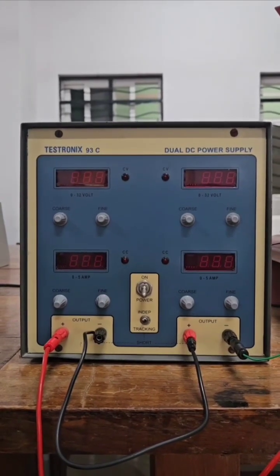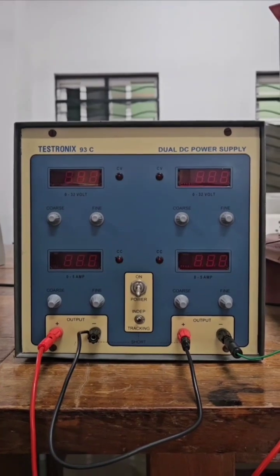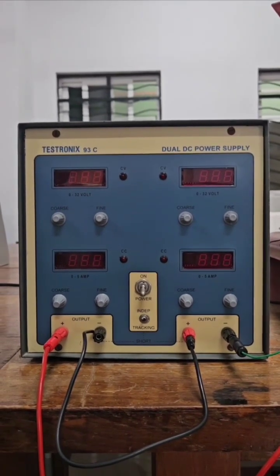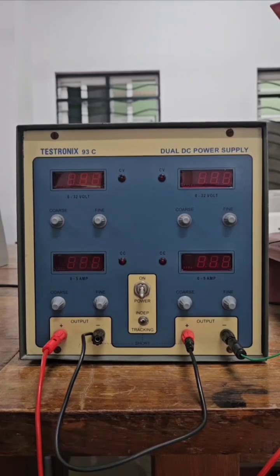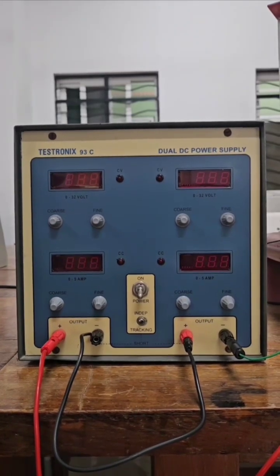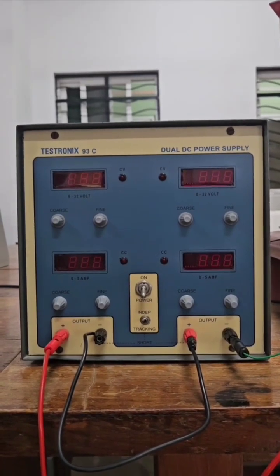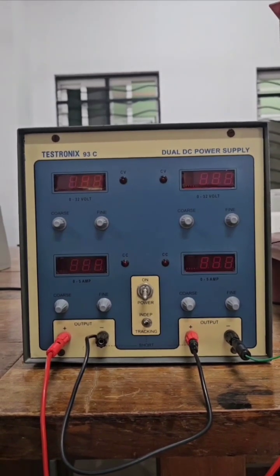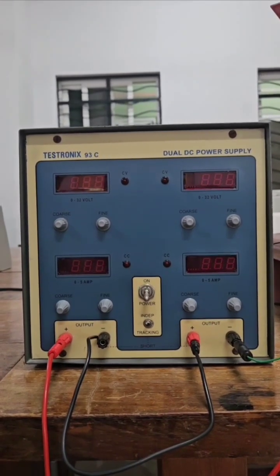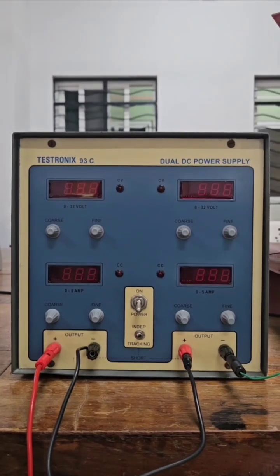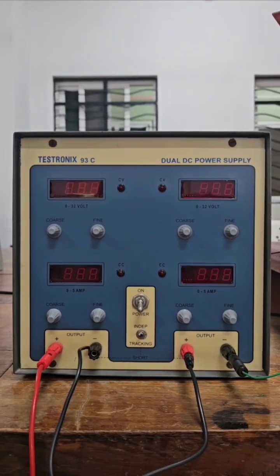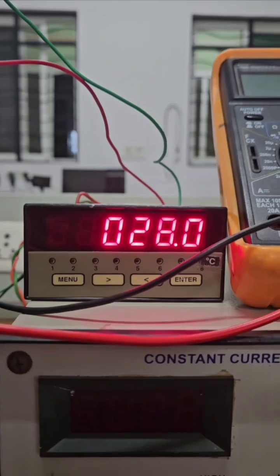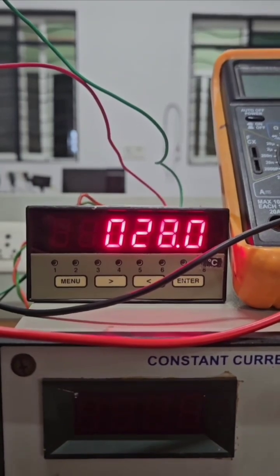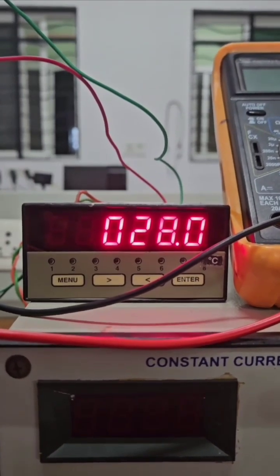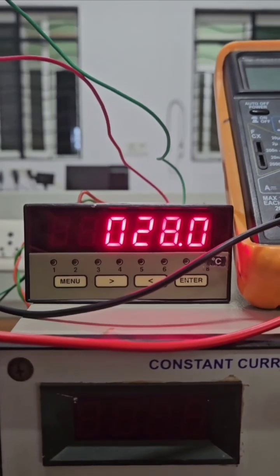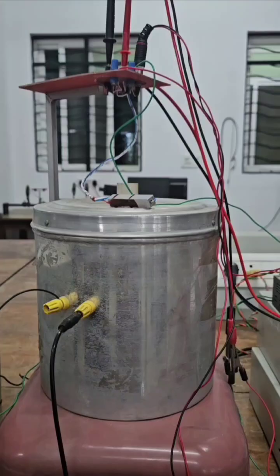So the apparatus required for this experiment, number 1 is the power supply. A regulated power supply is a source of DC electrical power, the voltage of which can be controlled between 0 and a maximum value. Such a power supply is required for heating a furnace and maintaining it at a given high temperature. So for this experiment, we set the voltage at 7 volts. Number 2 is the temperature controller. A temperature controller is used to set the temperature which the furnace is required to reach and to maintain the temperature within specified limits by controlling the heating power.